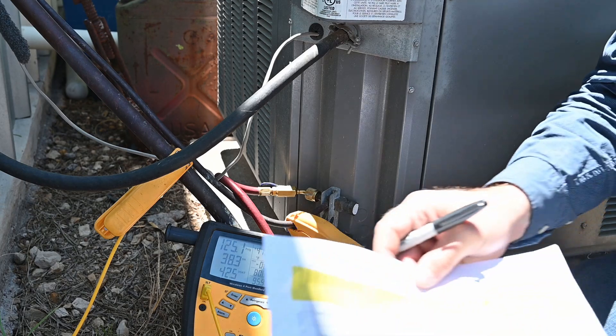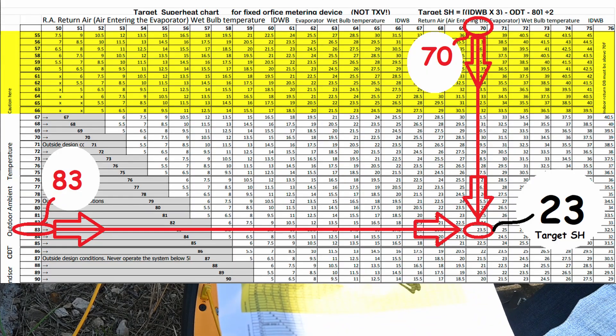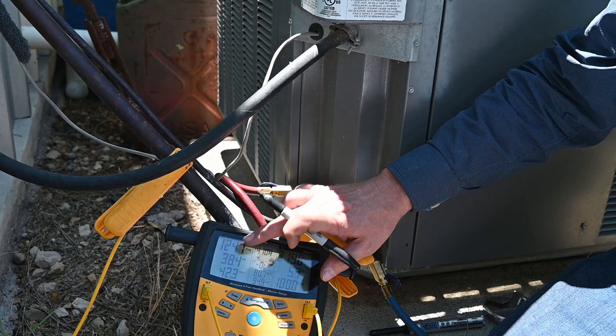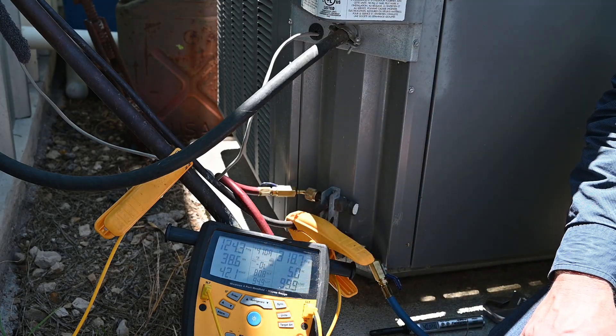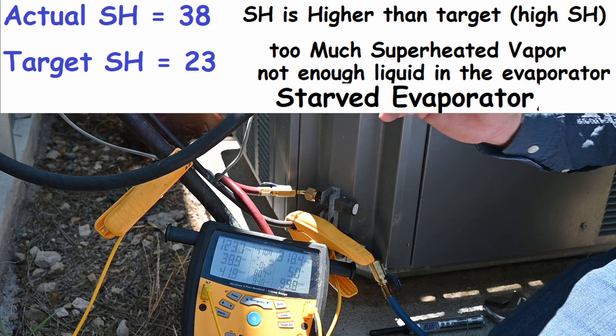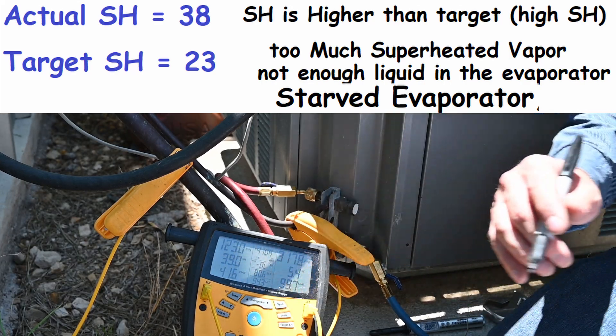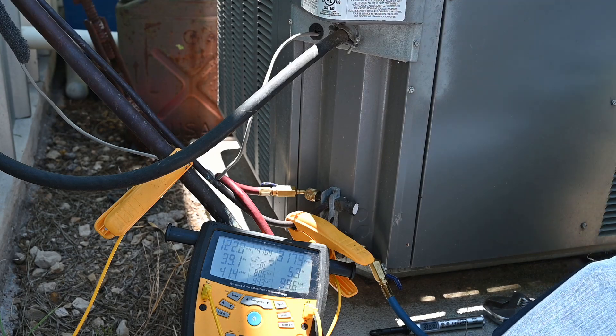I have a fixed orifice metering device. Inside, my return air wet bulb was 70 and outdoor dry bulb was 83, so it gives me a target superheat of 23 — that's where I want to be. My superheat is actually at 38. I have too much superheated vapor, which means there's not enough liquid in there. That means I have a starved evaporator — high superheat, starved evaporator.